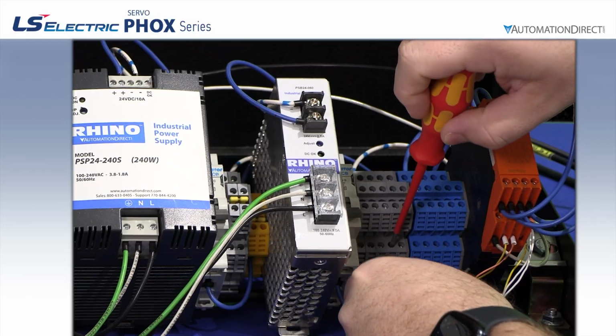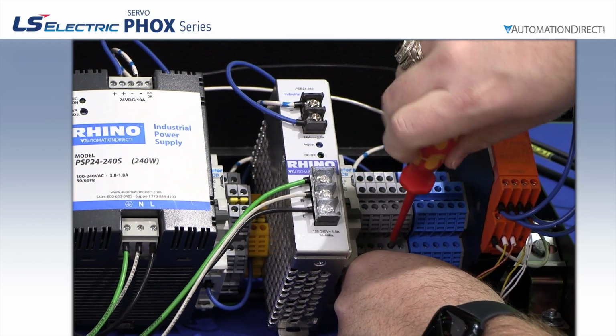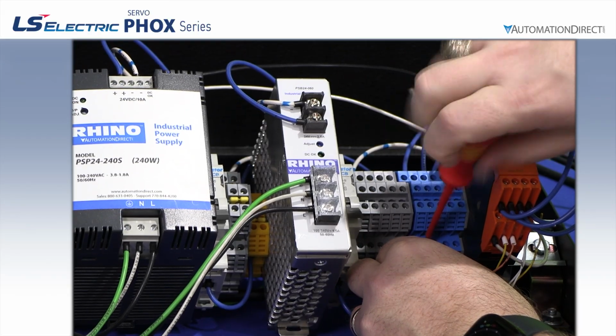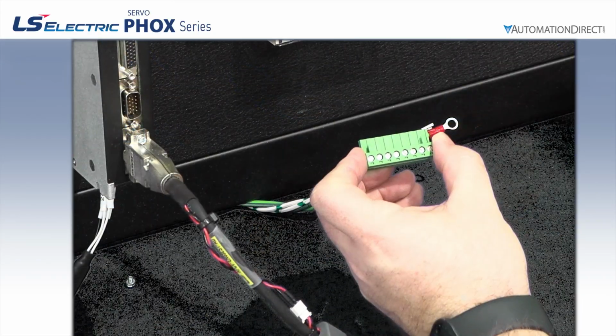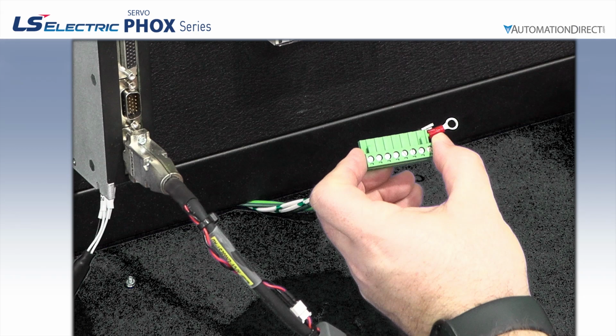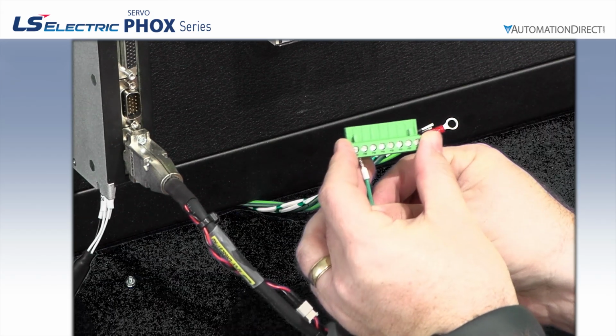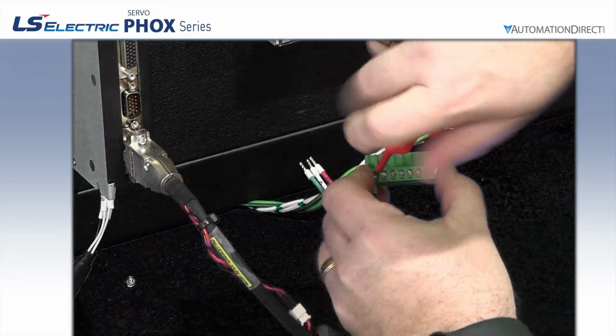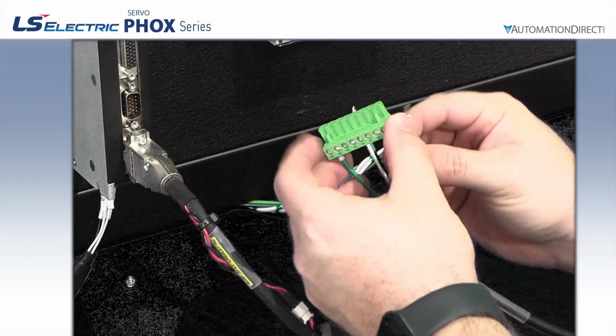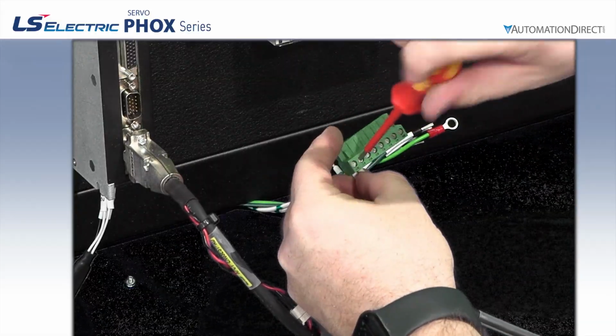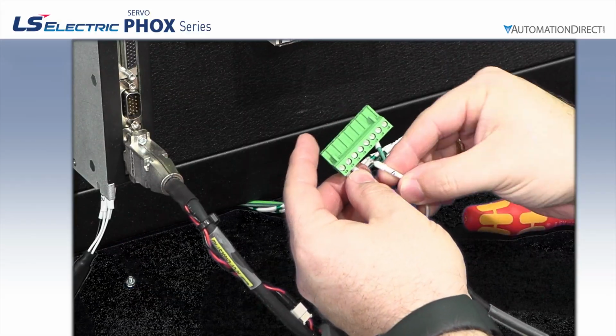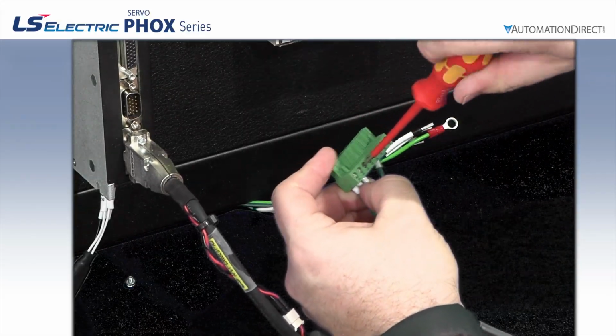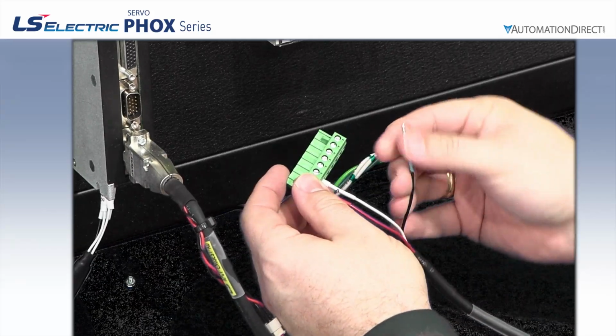For the motor brake cable connection, plug the 4-prong quick disconnect into the drive. Then connect the 2 24 volt DC leads to the positive and common terminals on the control power supply. These are polar sensitive, so ensure you don't connect them backwards. For the drive's motor power connection, use the green plug-in terminal block provided with the drive. It handles both the incoming DC power and the motor wires. This connector can only be installed one way, however you must land the various wires into the correct terminals. With the screw heads facing you, place the green motor ground wire in the far left position. The red U wire next, the white V wire after that, and the black W wire last.